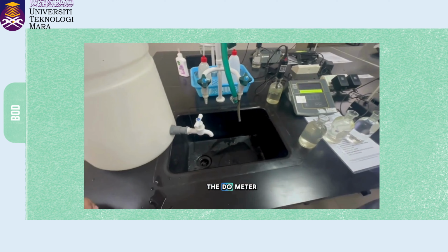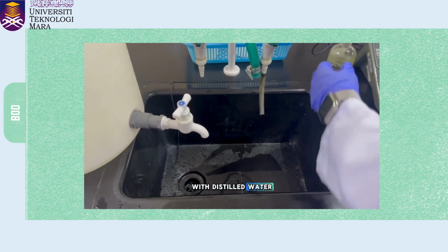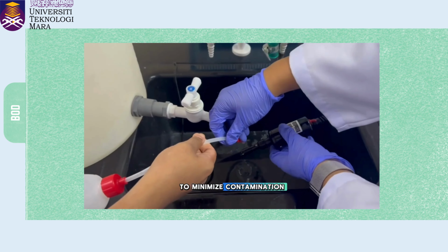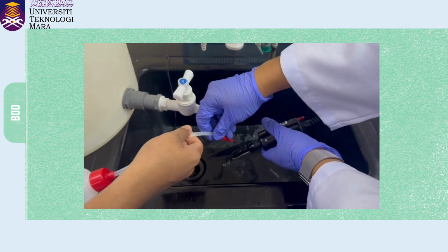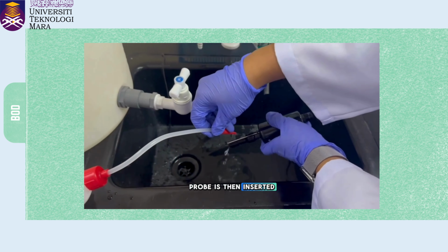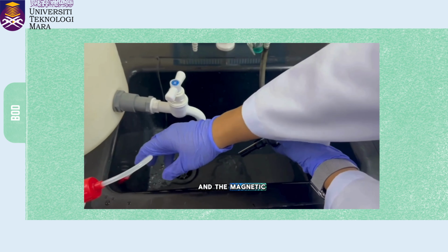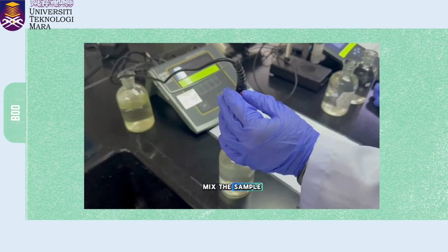We then switch on the DO meter and clean the probe with distilled water. This step is important to minimize contamination and ensure accurate readings. The clean DO probe is then inserted into the BOD bottle, and the magnetic stirrer at the probe is turned on to mix the sample gently.